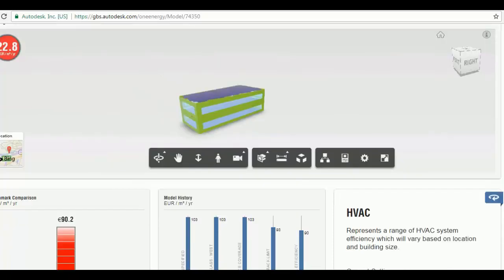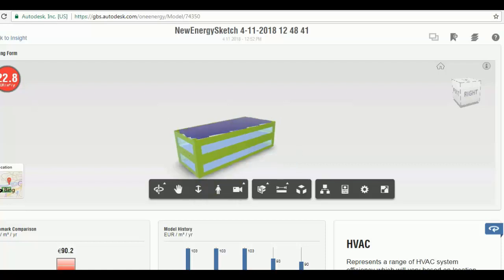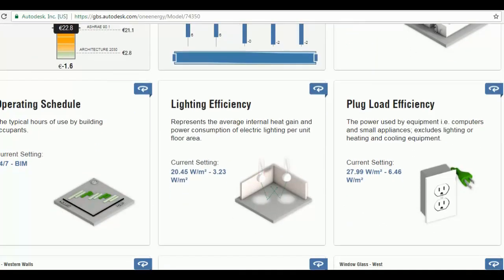So I can go down and I can see what the average of this building to run euro per square meter per year. So it's 22.8. And we can see to meet ASHRAE standards it needs to be 21.1. But if you want to meet the Architecture 2030 standards, which are US standards but are standards all the same, it's 2.8 per square meter a year.